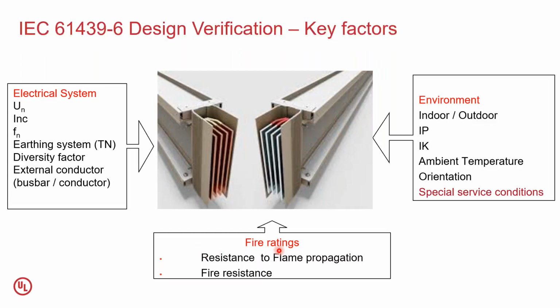So depending on that context, fire ratings have to be specified by the end user, and there are two basic ratings. One is resistance to flame propagation, that is, how quickly the flame gets propagated. The second rating is related to fire resistance. These are the key factors that will be used cohesively by the test lab, the manufacturer, and the end user to determine what type of busway one wants and how it is ultimately going to be evaluated.